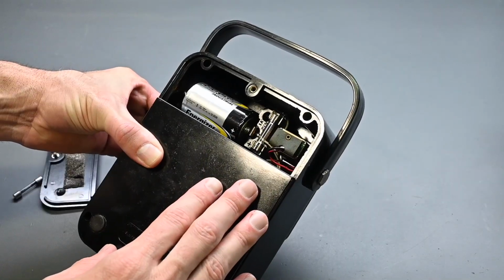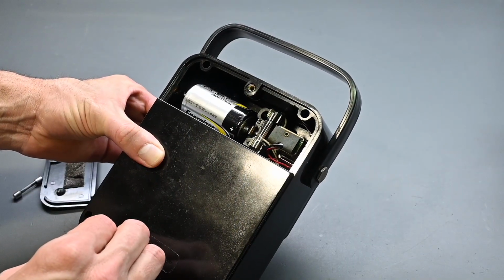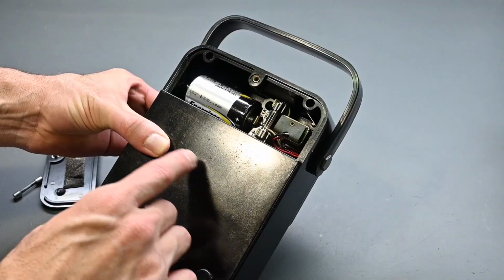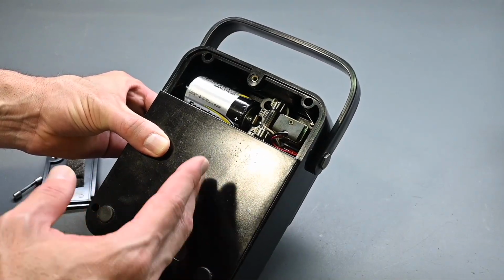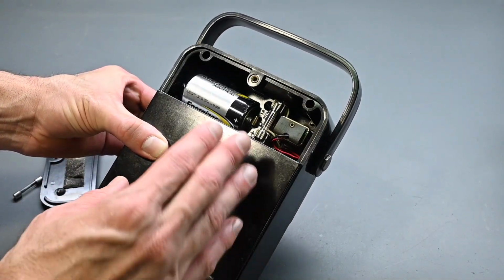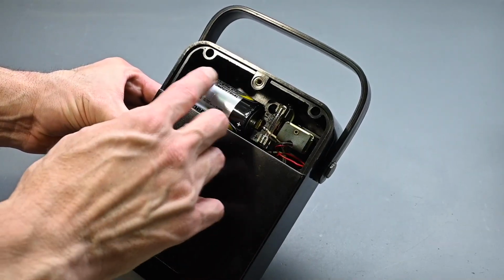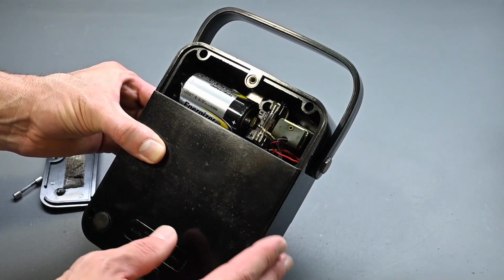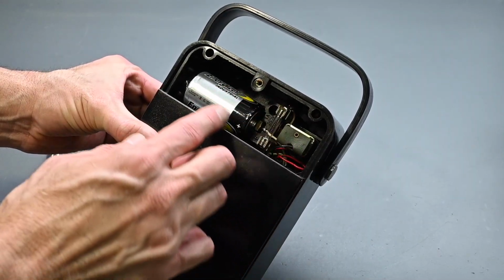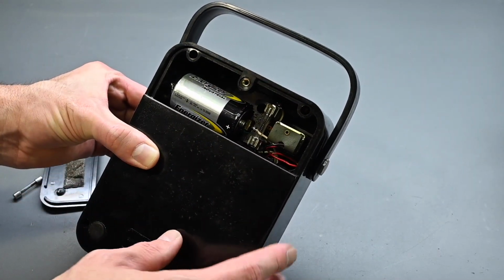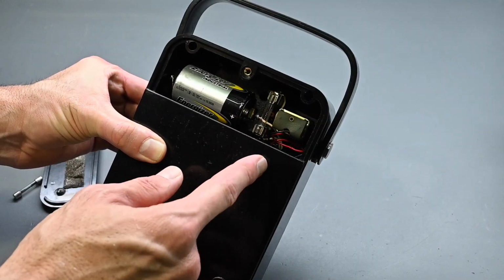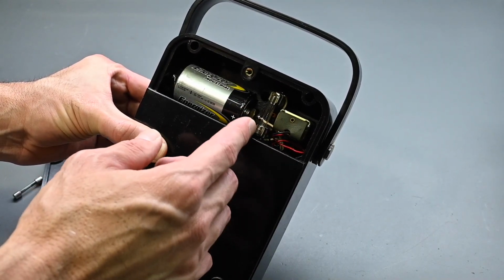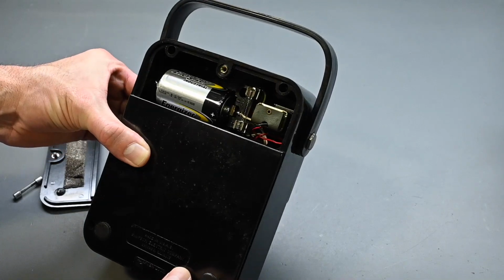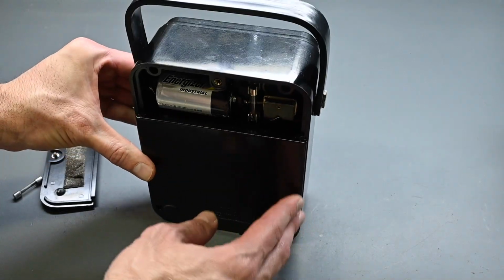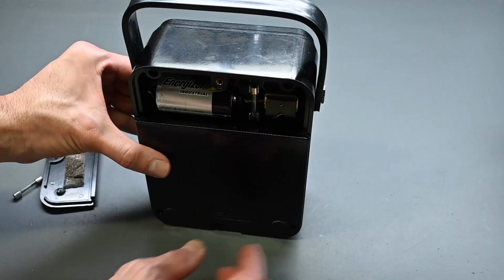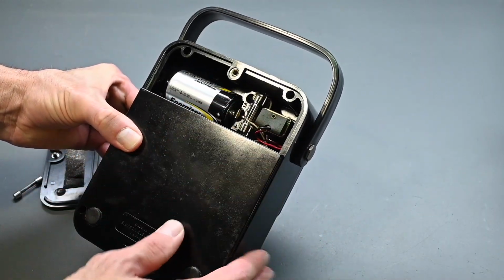So many of these meters were damaged over the years because of leaking batteries. In earlier series, the batteries were installed right around the circuit board, so if they leaked, they damaged the board and components. In this series and later series, the batteries are in a separate compartment, which is easier to change, and contains any leaking more to this area, but it can still cause a lot of damage. There's a little opening where the wiring passes through, and if there's enough corrosion and leaking it can still work its way down into the meter. A lot of times these meters are stored upright, so the corrosion works its way down. But everything looks very clean in here, so that was good to see.